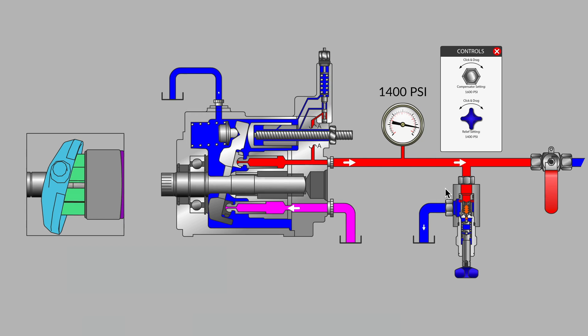The only purpose for a relief valve in this type of system is to respond to very sudden and short duration pressure spikes. The primary point of control for maximum system pressure in this type of system is the pump's pressure compensator.